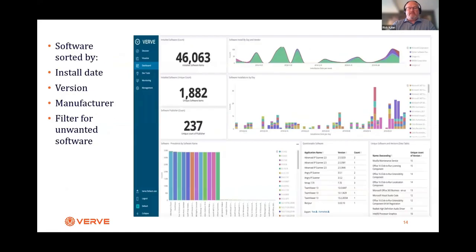We can also look at it from software. One of the things that many people don't realize is very low-hanging fruit and very easy to do is a lot of vulnerabilities and patches are related to things like Office products. And we often find that when people are installing Excel to look at ladder logic in an operational environment, they install the basic Office package. So you're getting Access and PowerPoint. Well, if we could go and get rid of all these different Office components, Visual Studio, etc., we would immediately also remove all the vulnerabilities that are typically mapped against those.